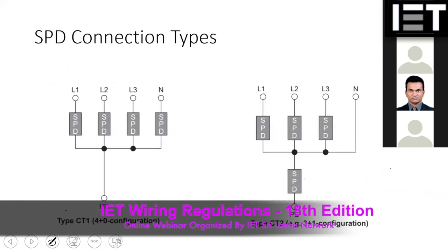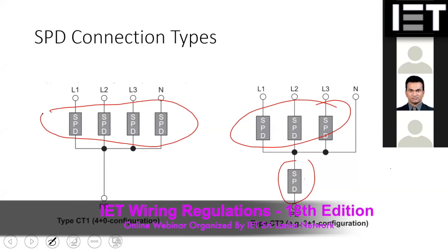And also the standard recommends certain types of connection patterns. Normally when we are using SPDs in the installation, we can use 2 arrangements. The first one we call a 4+0 arrangement, CT1. The second one we call a CT2 arrangement, which is 3+1. You can see there are 3 SPDs, and one from the neutral to earth. In the other one, all 4 lines, the 3 lives and the neutral, get 4 SPDs. If I ask what is the best way, whether the first one or the second one, which do you recommend for our installations? What do you say?